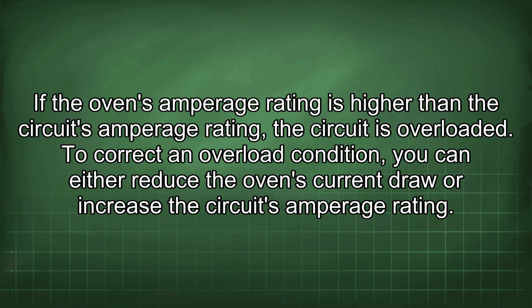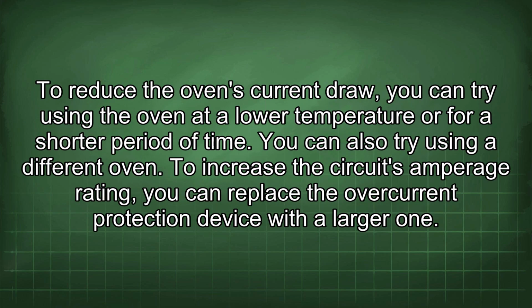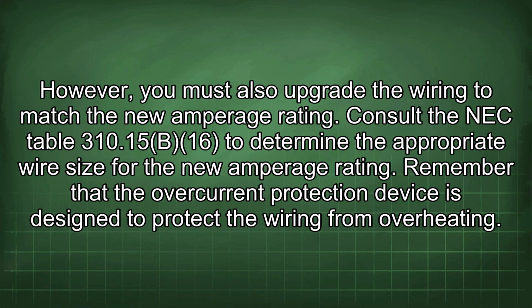To correct an overload condition, you can either reduce the oven's current draw or increase the circuit's amperage rating. To reduce the oven's current draw, you can try using the oven at a lower temperature or for a shorter period of time. You can also try using a different oven. To increase the circuit's amperage rating, you can replace the overcurrent protection device with a larger one. However, you must also upgrade the wiring to match the new amperage rating. Consult the NEC Table 310.15(B)(16) to determine the appropriate wire size for the new amperage rating.